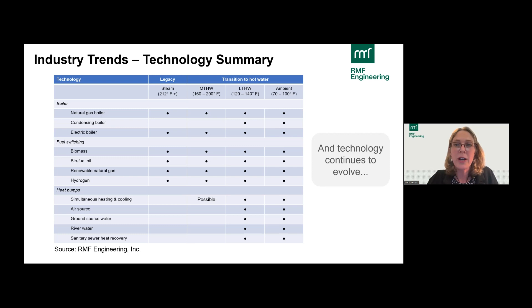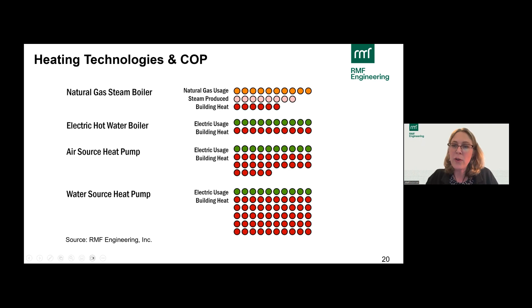You can see here, look at the green dots, which show how much energy you're putting in, versus the red dots showing how much energy you're getting out. An electric boiler gives you a 1-to-1 ratio: you put in 10 dots, you get 10 dots of heat out. As you move to more efficient heat pumps, air source and then even water source, you can put in 10 dots of energy on a water source heat pump and get up to 60 or 70 dots of energy out. That's a COP of 6 or 7 when those systems are really nicely balanced between heating and cooling. That's why people are really excited about heat pumps, why they're being incentivized, and why people are going so far as to transition entire steam systems to hot water so they can use very efficient heat pumps.